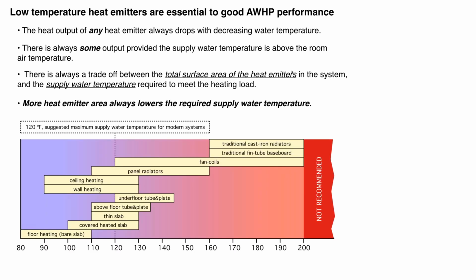And I put down here, just as a guideline, a wide range of water temperatures and some of the traditional ranges that these different heat emitter systems have been applied at. I'll start with the really high temperature stuff. There was a day when I would extend that graph out to about 230 degrees. There was a day when that was actually advocated: run your hydronic systems from a boiler with pressurized water, of course, at 230 degrees. And not only is that a safety issue, if you lose the pressure, you have instant steam flash. That was done strictly in the days when houses literally had no insulation in the envelope, and they were trying to keep the size of the heat emitters as low as possible.